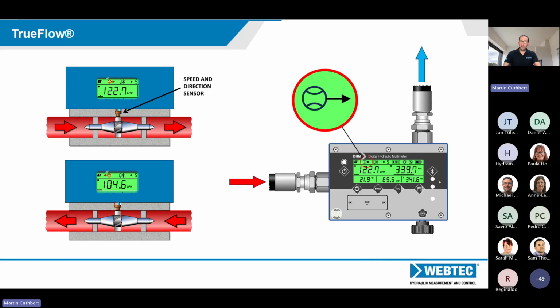Particularly useful. Sometimes it's easy to look at a hydraulic circuit and see which way the flow should be going through the circuit, but when presented with a whole load of hoses as you pipe up a tester, it's not always entirely obvious whether you got it right or not. The testers are fully bidirectional, so they'll measure flow in both directions. This way you can see which way the flow is going. On certain hydrostatic transmissions, you may have the flow going in both directions and want to test it in both directions. And this way it will record which direction you were testing at which time.